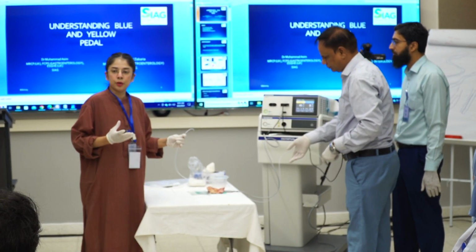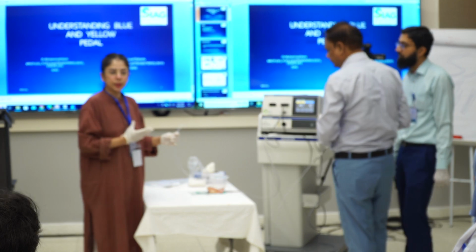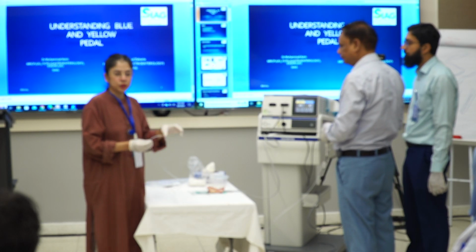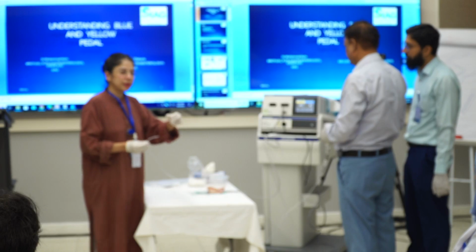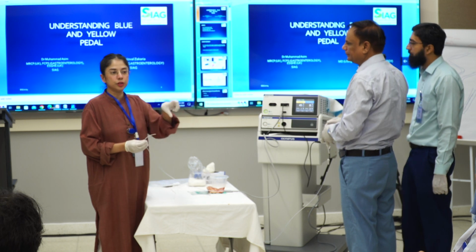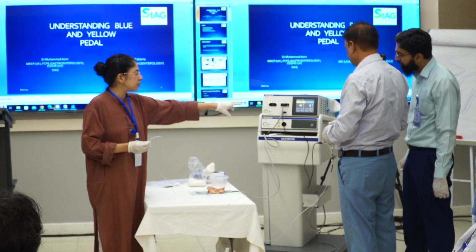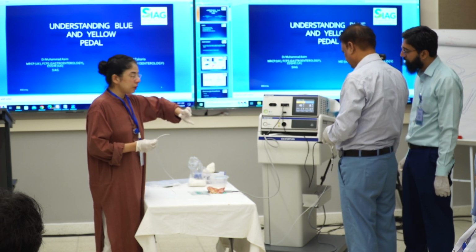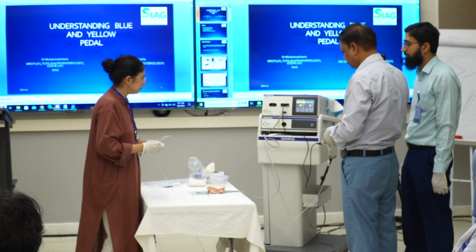So you remember, while we're focusing on the camera, effect basically determines how much coagulation is inside your cut. Okay? So effect 1 basically means there's no coagulation happening. Effect 2 would mean there is some. 3 would mean the intensity of the coagulation is increasing, not the duration of the clot. And so right now we're just going to do pure cut, and we're going to keep it on a high voltage, and let's see how the cut manifests on the chicken.